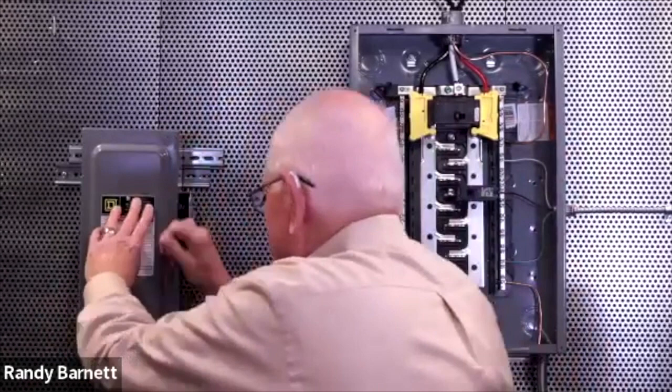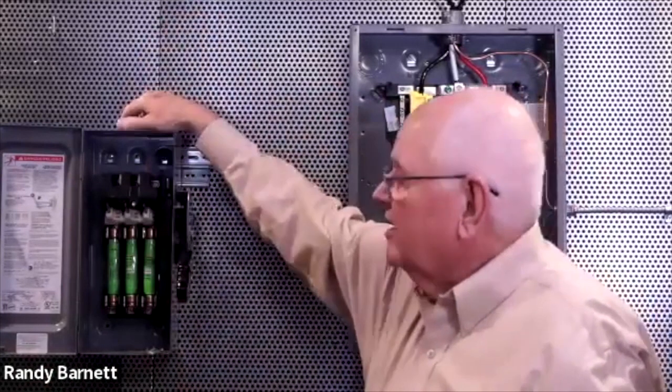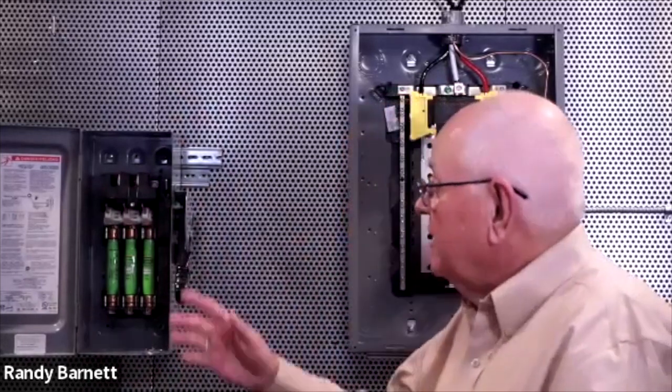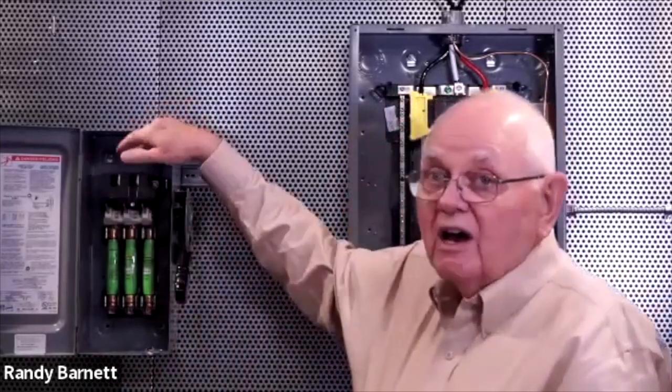Now, let's take a look at this disconnect switch as well. We open up the disconnect switch and I can see the blades down below. If the disconnect has been wired properly, of course, the incoming line power would come into the top of the disconnect. And then when I open the blades, I interrupt the power on down to the rest of the circuit. So everything from the blades that I see on down should be de-energized. Of course, I say that no matter what I'm talking about, we're always going to follow our proper lockout and tag out procedures and do our live-dead-live tests and so on. But anyway, the live terminals would be up top here.